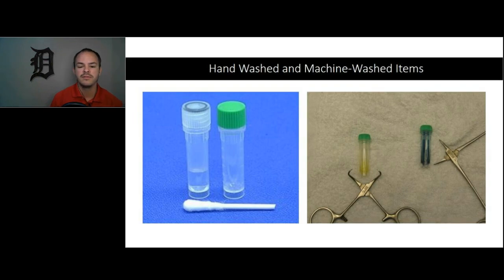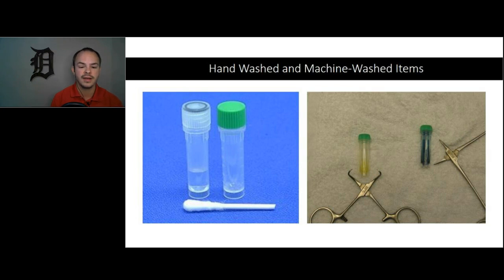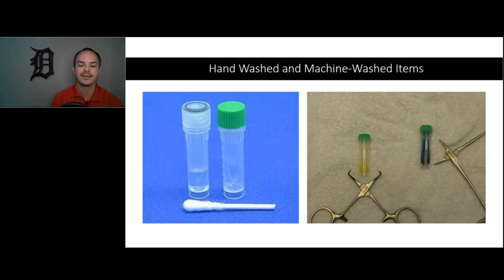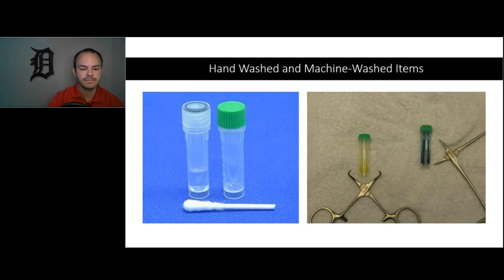Here is an example of a simple cleaning verification test. These are used for checking challenging items to be cleaned, whether in an automated washer or by hand. This particular test shows the presence of hemoglobin. If it turns positive, that instrument needs to go back for a repeat cleaning — it should not proceed to prep, pack, and sterilization. This helps us see soils that may not be easy to see with the unaided eye, and can confirm whether staining is actually blood. You can also get protein tests and ATP tests — all part of the cleaning verification line.